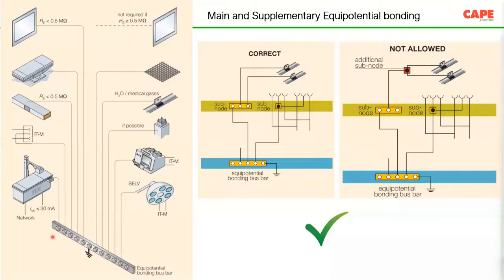You have to have a bus bar large enough to accommodate each and every connection separately. So individual earthing means each and every medical item must be connected to this bus bar separately. This means you are not supposed to make a loop. Then you can see that some of the biomedical equipment are connected. The medical IT system is connected to the bus bar. The cable management system is connected to the bus bar. The floor mats, electrostatic mats, or some mats, if available, are also connected to this bar.